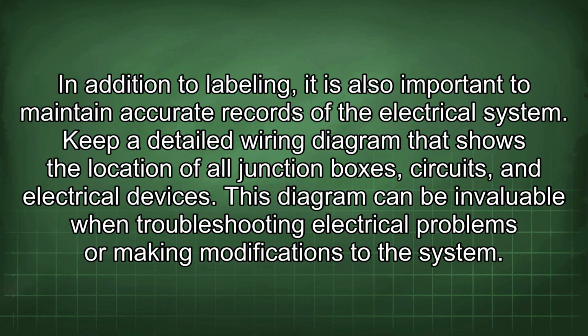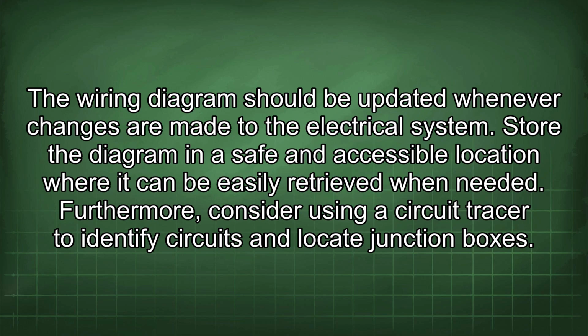In addition to labeling, it is also important to maintain accurate records of the electrical system. Keep a detailed wiring diagram that shows the location of all junction boxes, circuits, and electrical devices. This diagram can be invaluable when troubleshooting electrical problems or making modifications to the system. The wiring diagram should be updated whenever changes are made to the electrical system. Store the diagram in a safe and accessible location where it can be easily retrieved when needed.